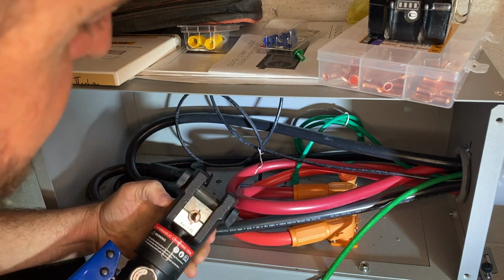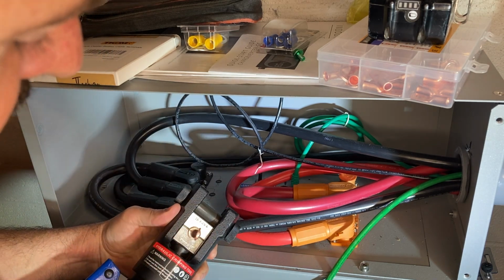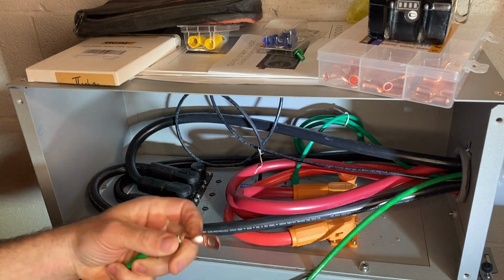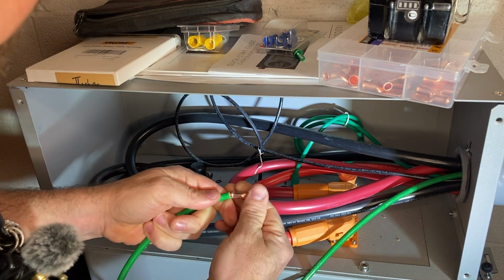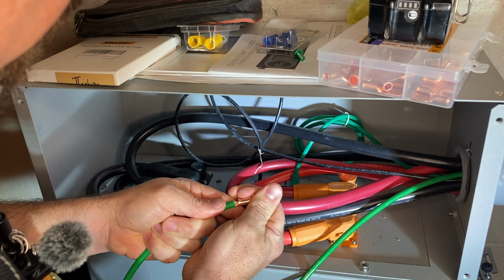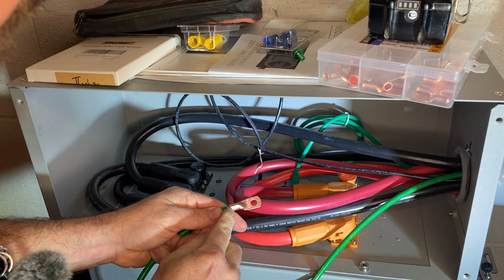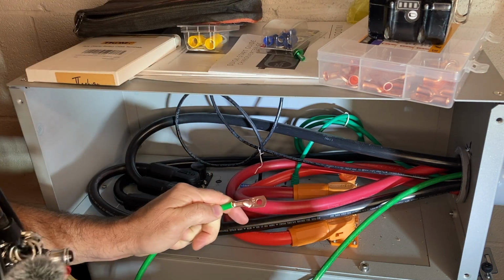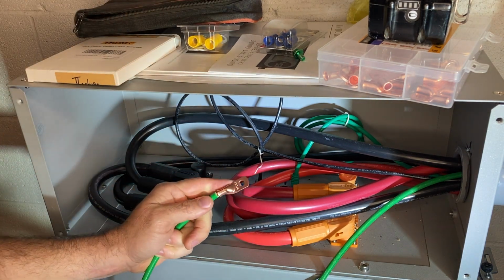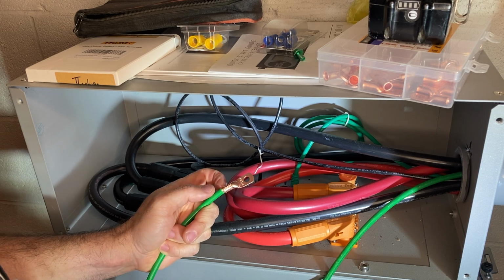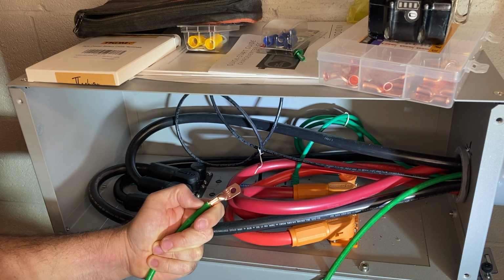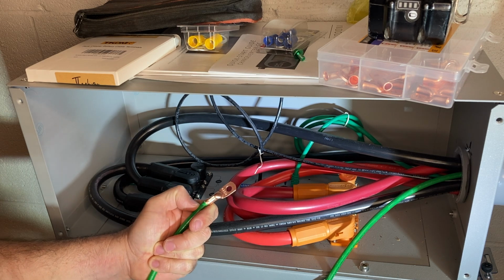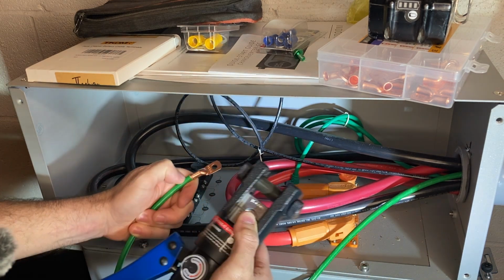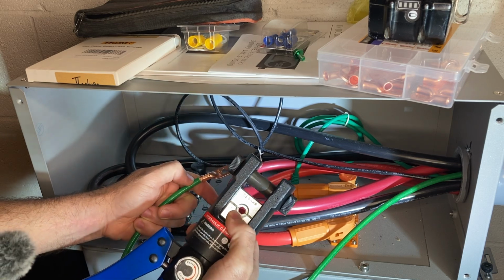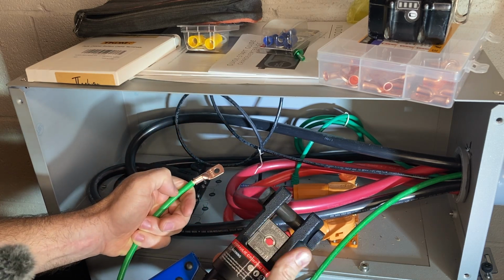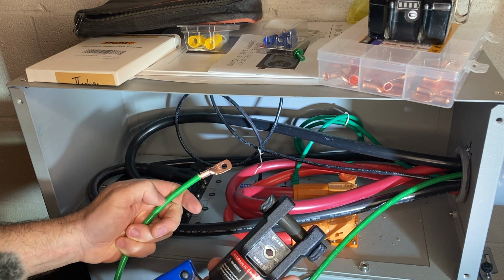That tells me that's just not going to be tight enough. This is a 6 gauge wire, a 6 lug, but it seems like these have been a little loose. Yep, this one is as well. So we're going to bring the die down to a number 8 die for this one. I think it really depends on the lug and the thickness, whether it's plated or not. But for whatever reason, maybe it's just these Chinese dies aren't actually 6 gauge, it seems like they don't match up between different manufacturers.